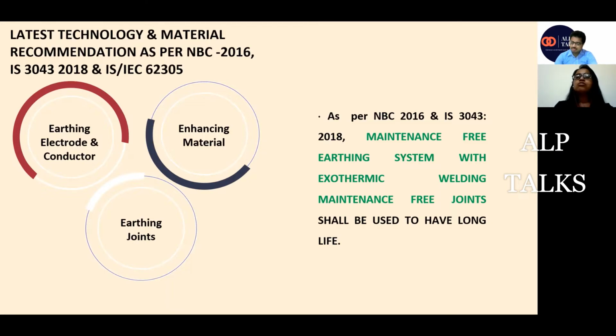In these 2 years, soil resistivity can vary, first of all. And if I have done the calculation using an Excel sheet, I am not able to validate the design. I don't know the nature of my soil at that location. I just have a resistivity value, because when we do soil resistivity testing, we get a number of resistivity values. But Excel sheets have this disadvantage that we can put only one value in the formula. So either we take the average of all the resistivities, or we take the highest one. With the highest resistivity value, we are over designing the system, which unnecessarily increases the project cost.